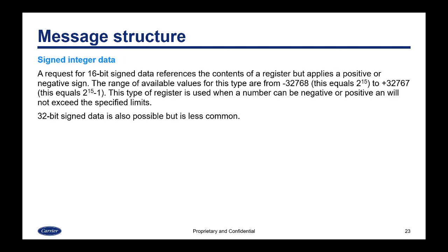A request for 16-bit signed data references the contents of a register but applies a positive or negative sign. The range of available values is from negative 32,768 (which equals 2 to the power of 15) to positive 32,767 (which equals 2 to the power of 15 minus 1). This type of register is used when a number can be negative or positive and will not exceed the specified limits. It's also possible to create 32-bit signed data, though it is less common. You would use signed data whenever the value in the register could be negative.